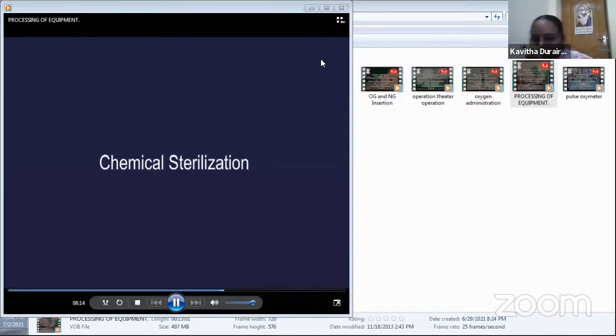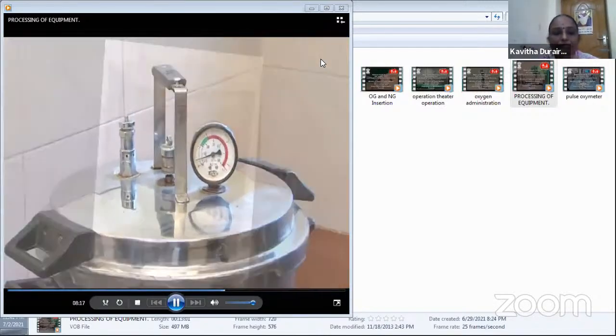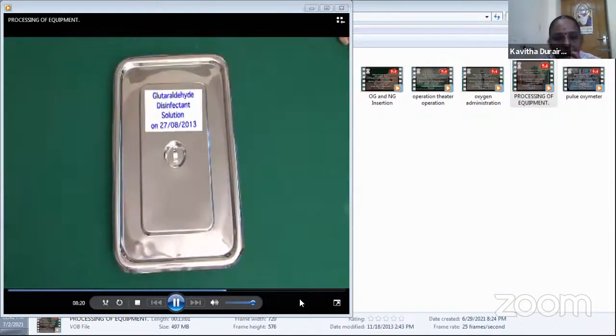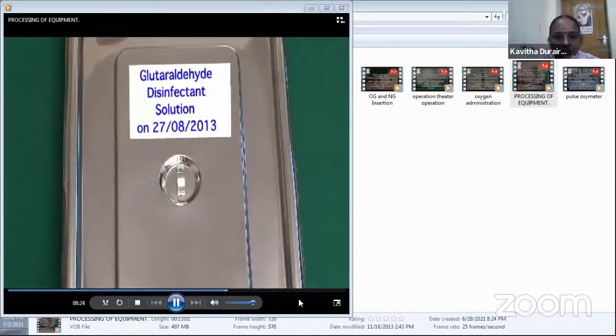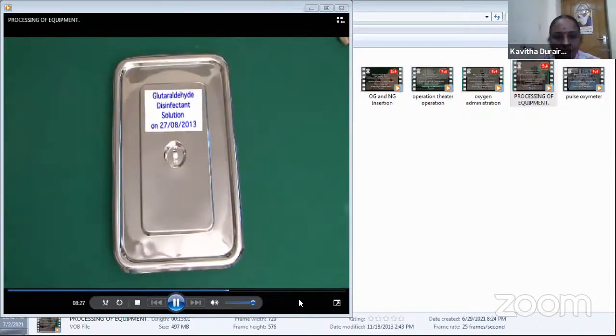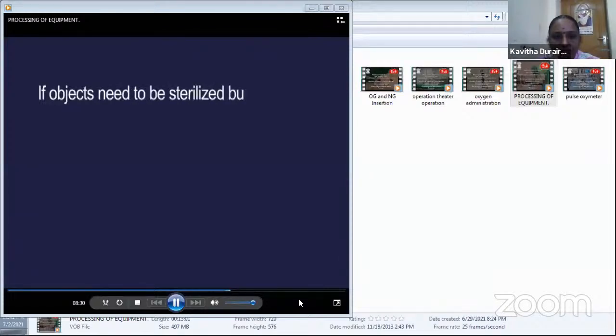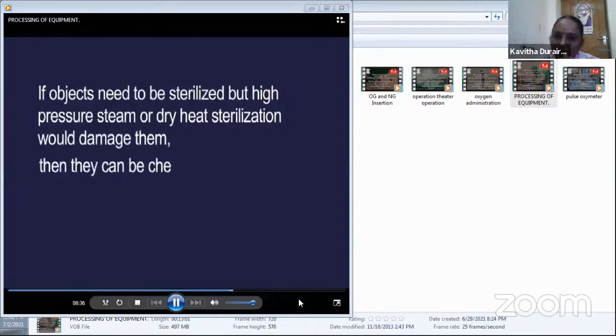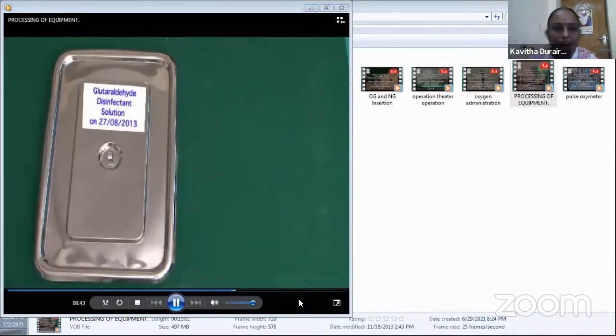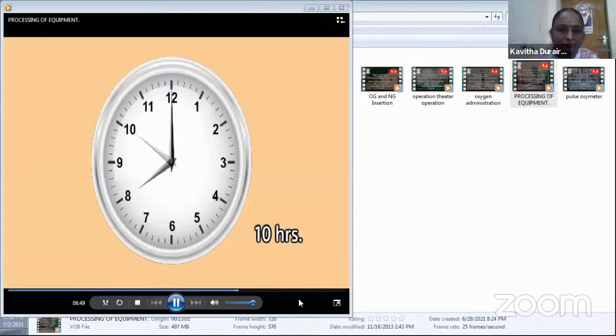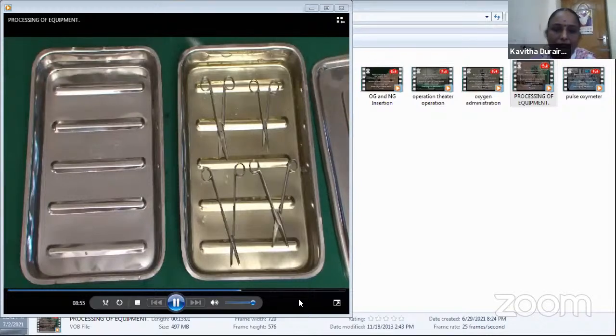Chemical sterilization. An alternative to high-pressure steam or dry heat sterilization is chemical sterilization, often called cold sterilization. If objects need to be sterilized, but high-pressure steam or dry heat sterilization would damage them, then they can be chemically sterilized. For high-level disinfection, the instruments are soaked for 20 minutes, while for sterilization, prolonged exposure for a minimum of 10 hours is needed. Remove the equipment with a sterile Cheatle forceps and rinse with sterile water.